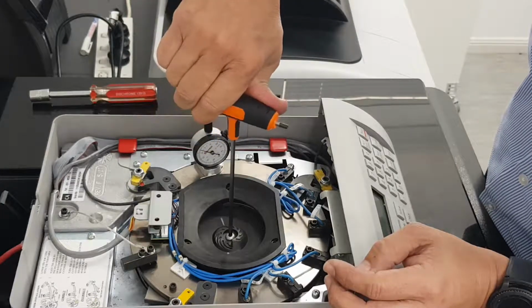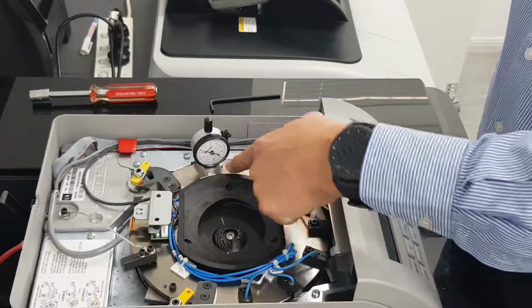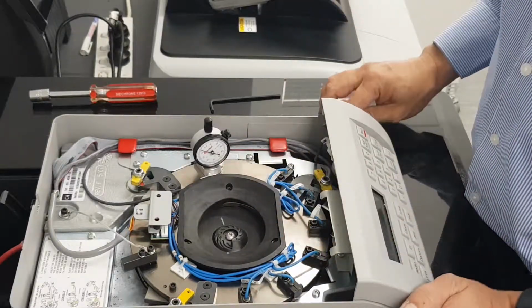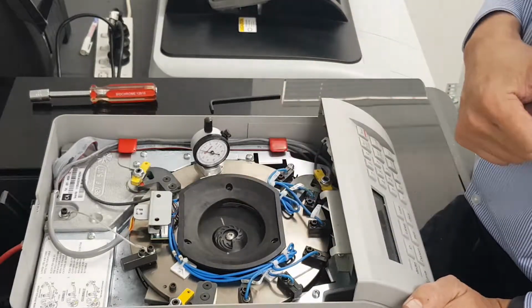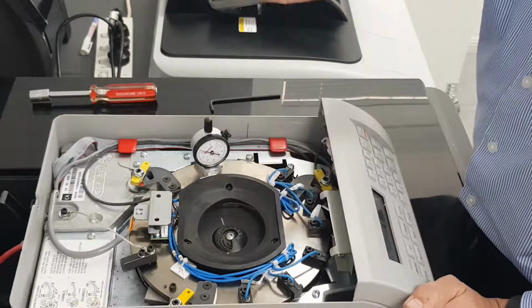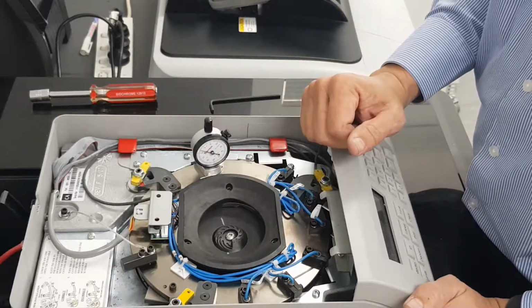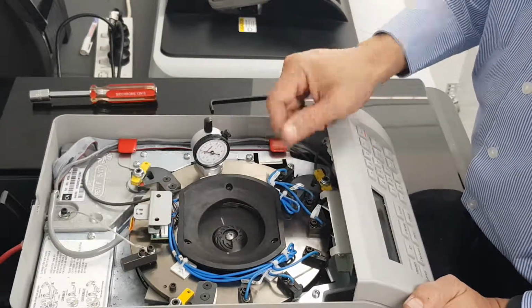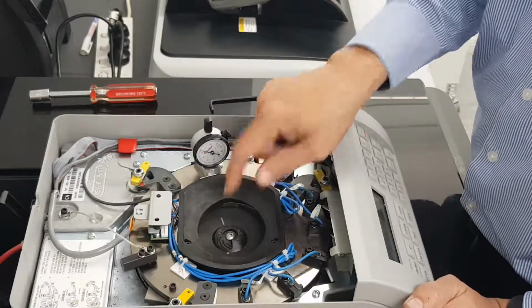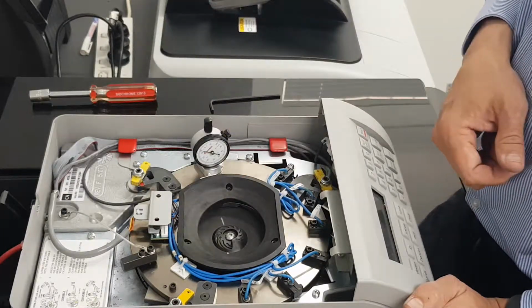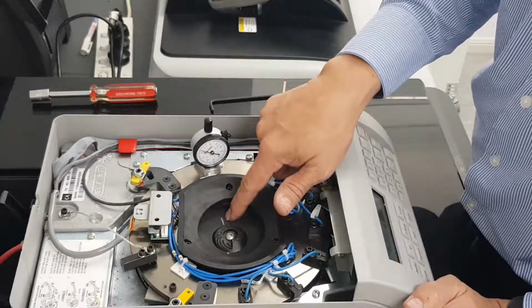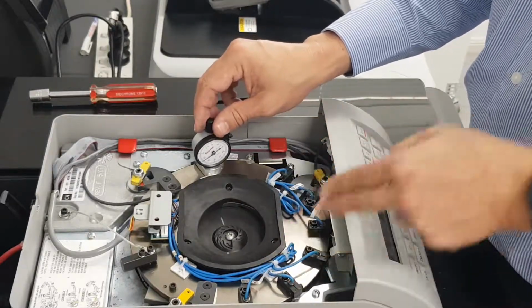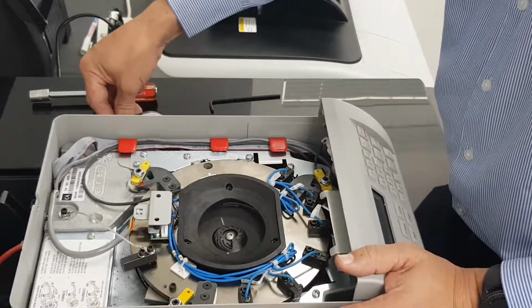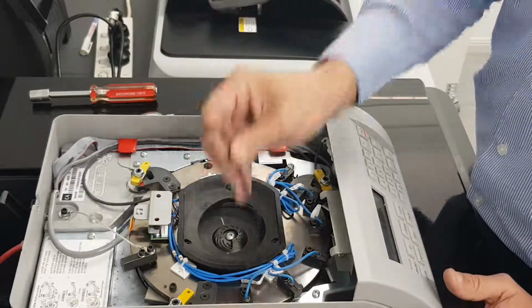And our point is exactly where the little white mark is, in line with the dial gauge. So we know that's our high point, and we've just marked it with a little bit of white pen. You can use whatever you like. I've also used a little bit of electrical tape, just cut into a strip, and then I can just remove it afterwards. Okay, so that's our high point. That will be our reference for the rest of the calibration points. I'll just put that aside and I can remove our sensors out.